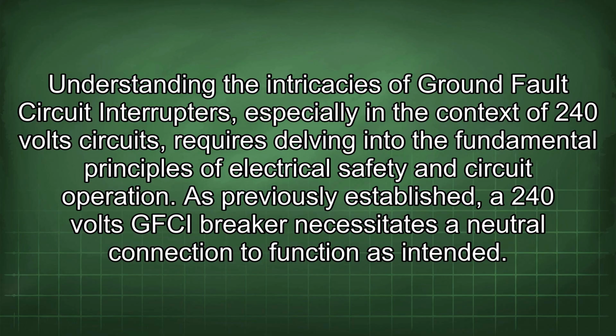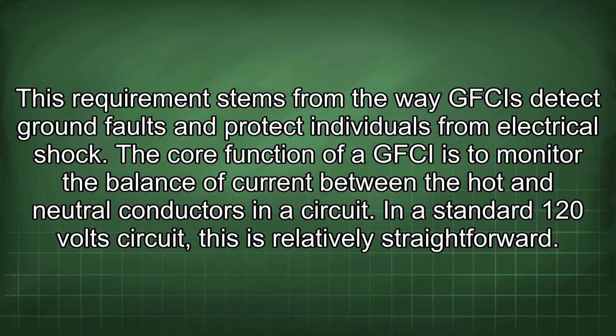Understanding the intricacies of ground fault circuit interrupters, especially in the context of 240-volt circuits, requires delving into the fundamental principles of electrical safety and circuit operation. As previously established, a 240 volts GFCI breaker necessitates a neutral connection to function as intended. This requirement stems from the way GFCIs detect ground faults and protect individuals from electrical shock.